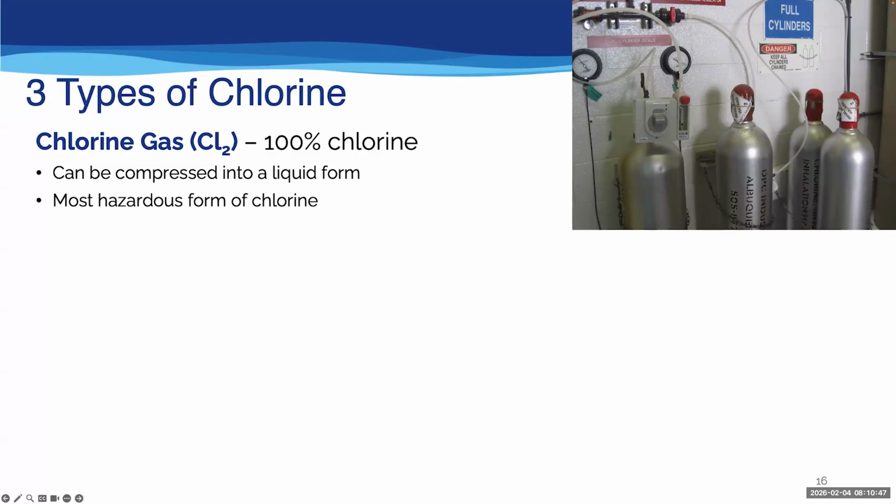It's 100% chlorine. It comes in compressed form, where it's liquid, basically in containers like the ones you see there on the right. Those are 150-pound cylinders. They come in 150-pound cylinders, and then 1-ton cylinders. Those cylinders there are about 53 inches tall. The 1-ton cylinders, 8 feet long, 3 feet in diameter. The bigger ones are used typically by medium to large municipal systems. A ton of chlorine is a lot. Even 150 pounds is a lot, and it's under pressure.